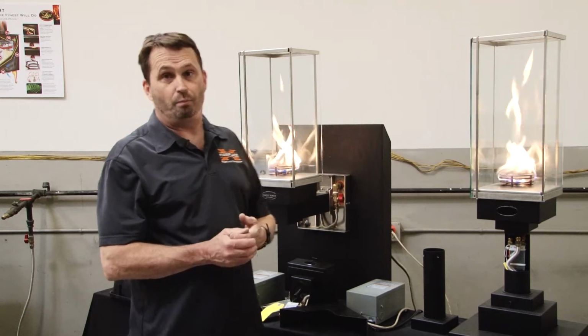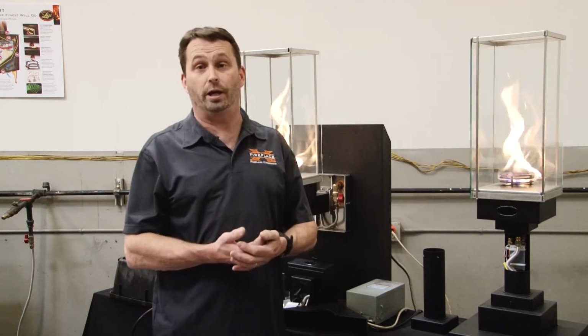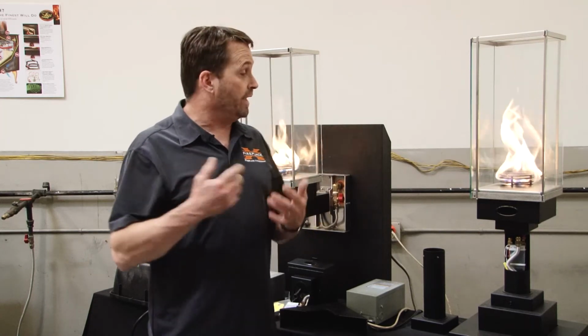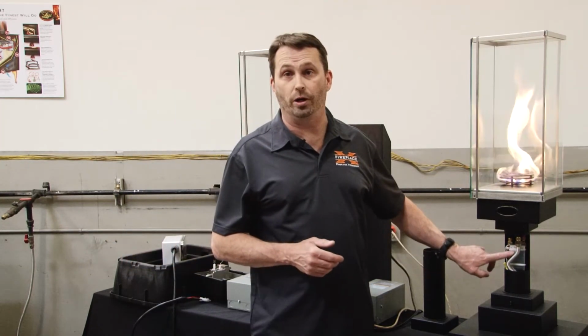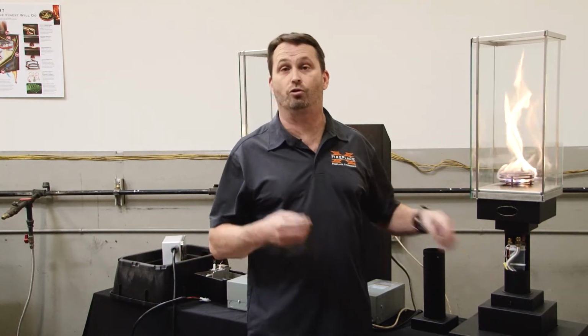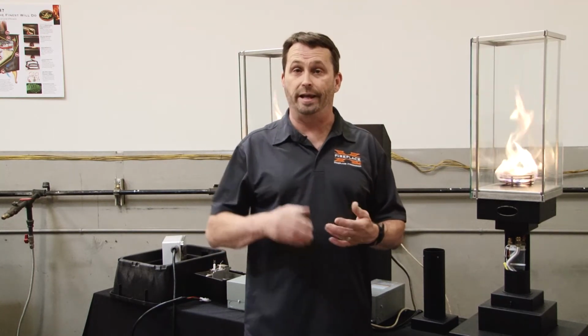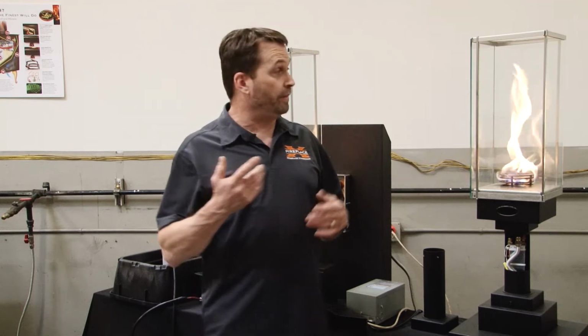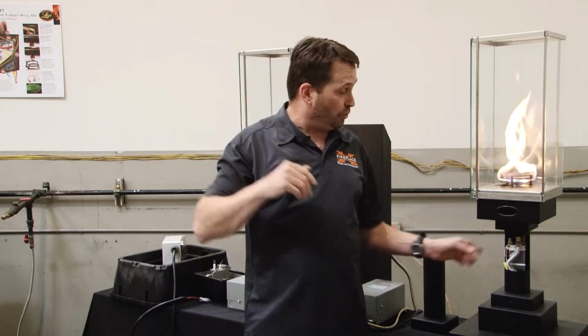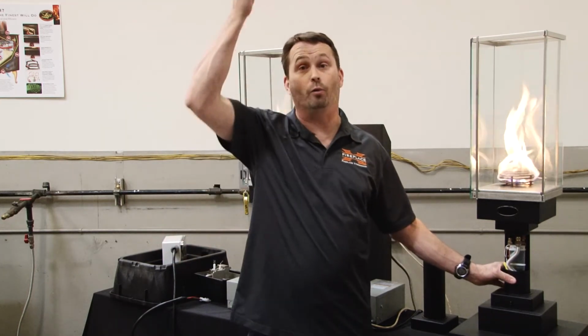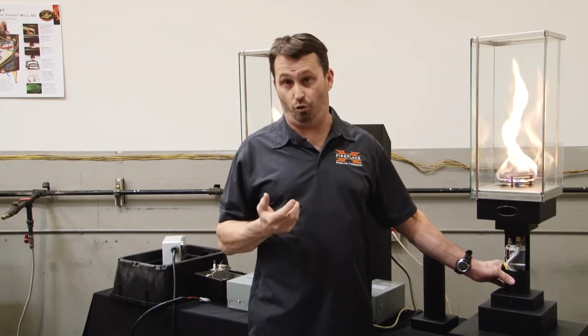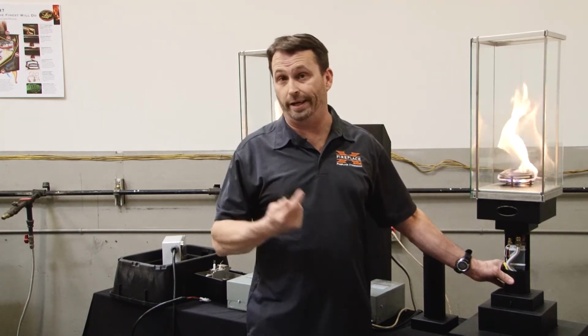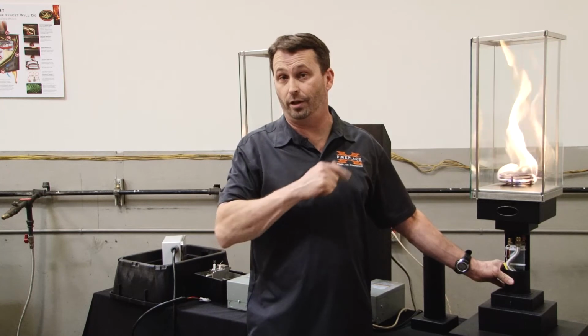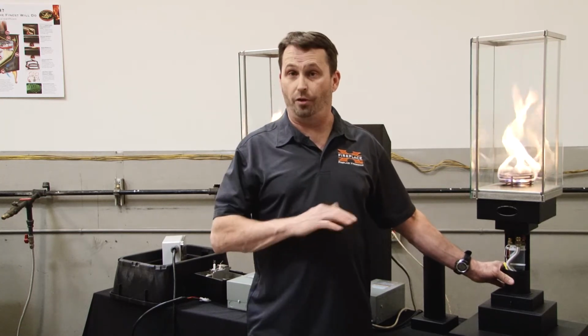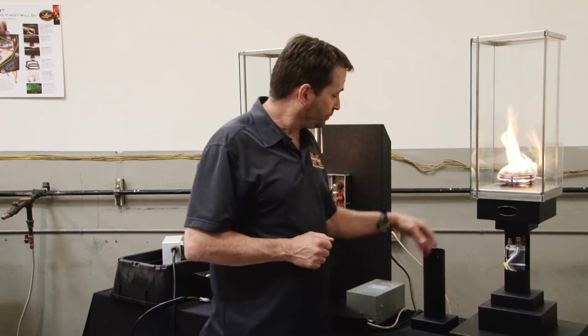And before, with the old system, you would get a couple of melted wires, but in the new system we have all the components directly below the head assembly. So it's really important that any penetration into the building is completely sealed. That also applies if you're doing a post or a pillar mount on the roof of a residential or commercial building. Make sure that where the gas line and the power come out of the building into the base of the unit, those get completely sealed.